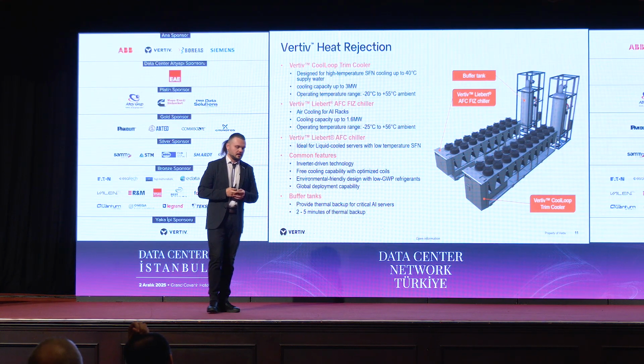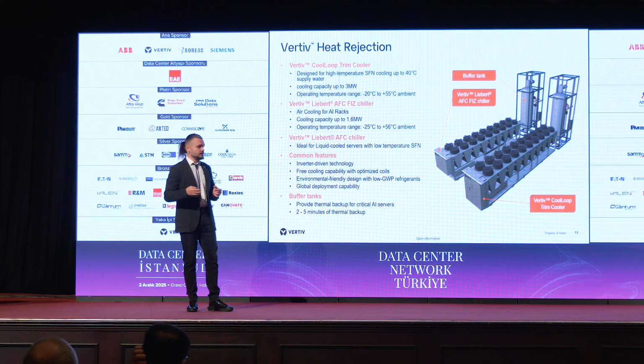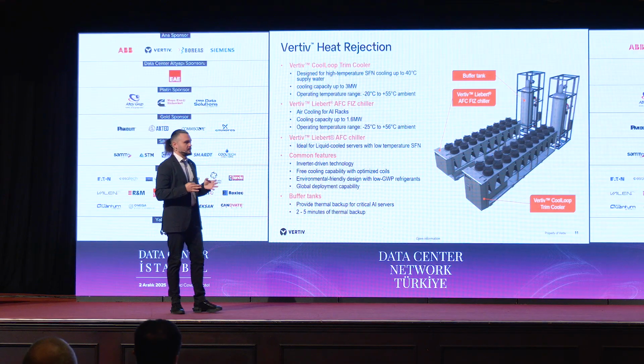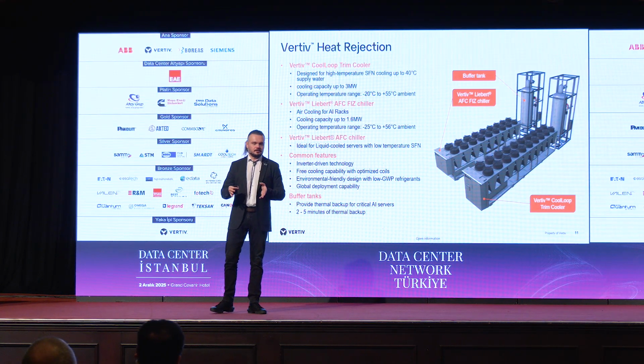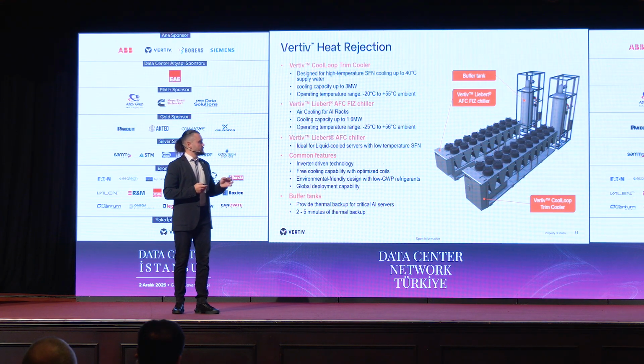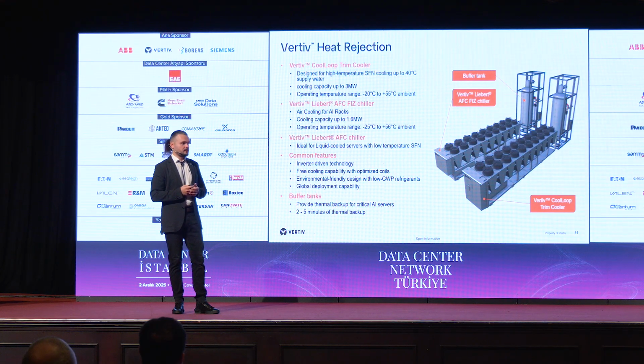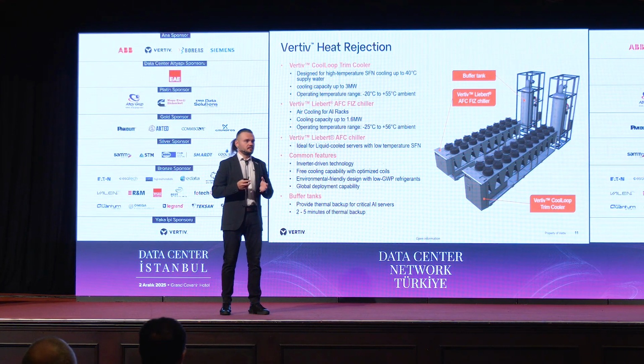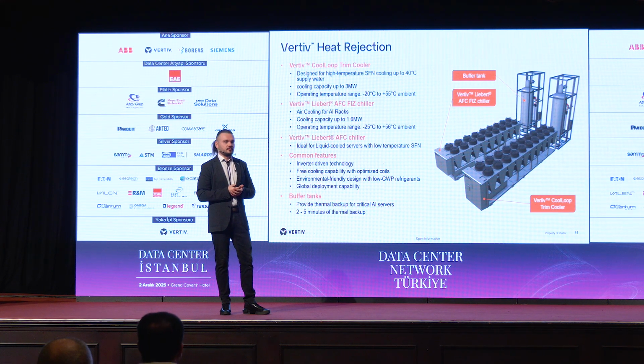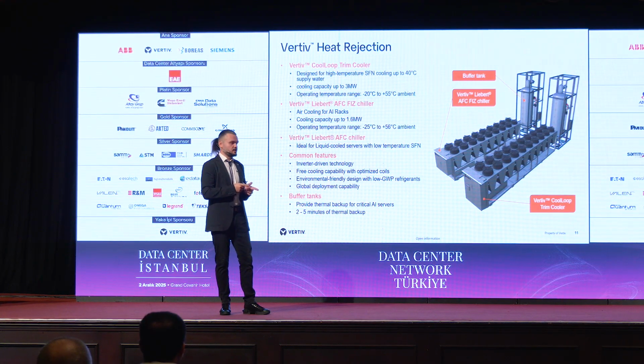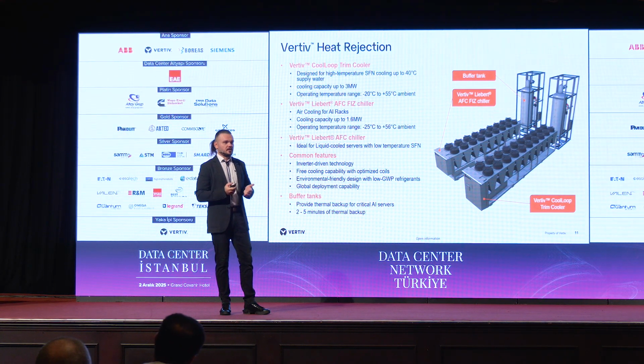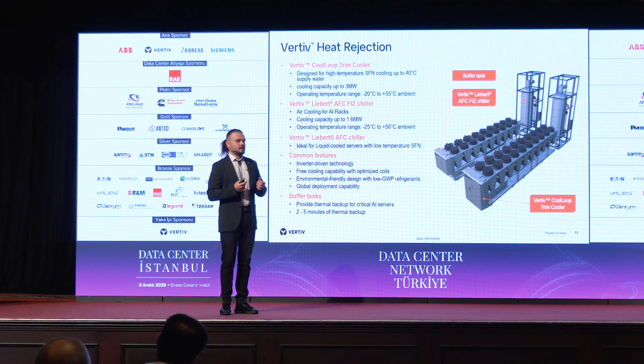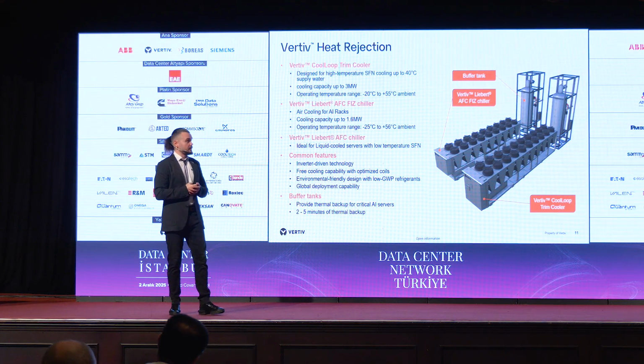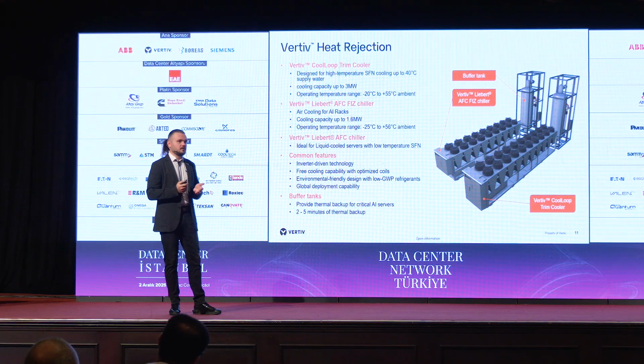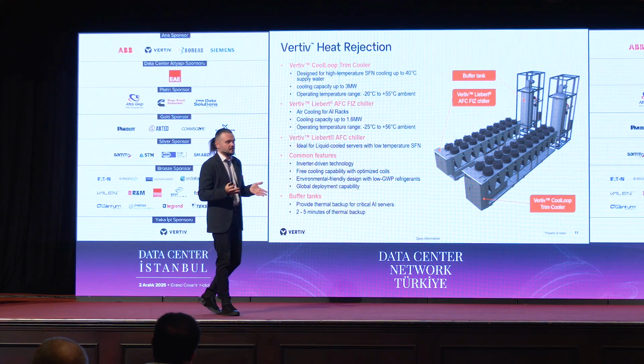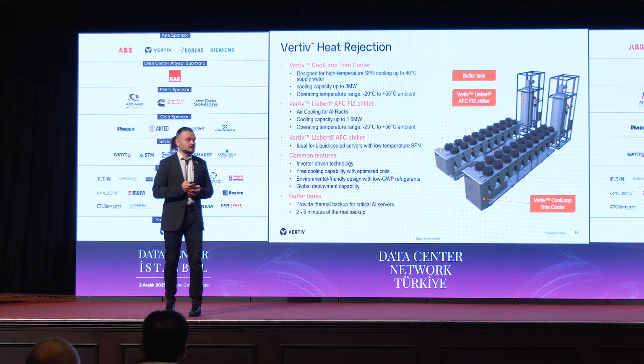The benefit of this unit, and its special design, is that it's basically larger. It has embedded pumps, so you do not need to oversize your hydro module to accommodate all the pumps. And at the end of this unit you see the water tanks, so it's also a part of the prefabrication. The platform usually has tanks to provide 3 minutes of autonomy time, because during the switching period from the grid to the genset we need to keep the system up and running. The CDUs need to pump the water, the chiller pumps need to operate, and it means we need to provide continuous cooling, not because we are trying to reach Tier 4 from Uptime Institute, but because we have to, because the equipment will overheat and it will cause a lot of problems.